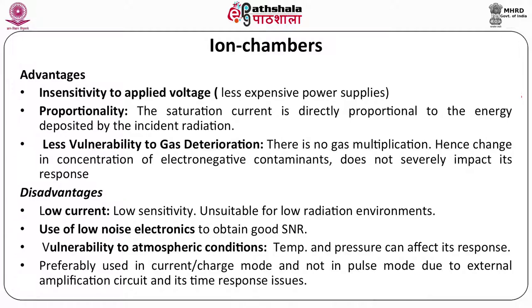The disadvantages of ion chambers include low current — there is no amplification, so inherently they are low-sensitivity detectors, unsuitable for low radiation environments. You need low-noise electronics to obtain a good signal-to-noise ratio. Another disadvantage is vulnerability to atmospheric conditions: if temperature and pressure within the detector change, the density of air changes, altering the amount of ionization produced and requiring different calibration. Ion chambers are preferably used in current or charge modes, not pulse mode, due to external amplification circuit and response time issues.